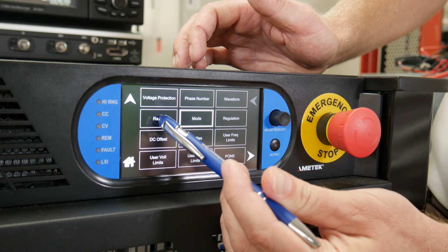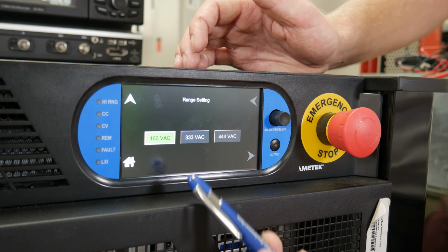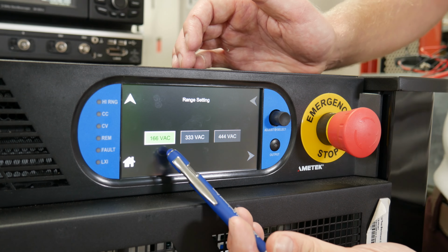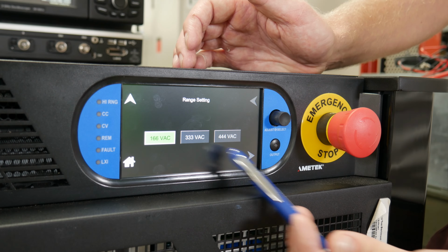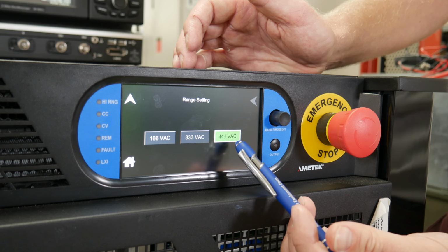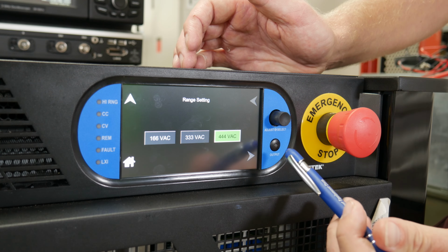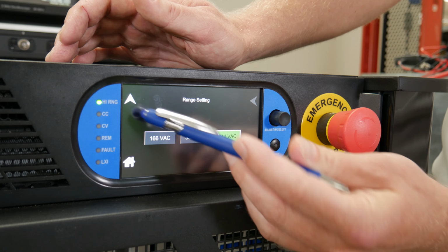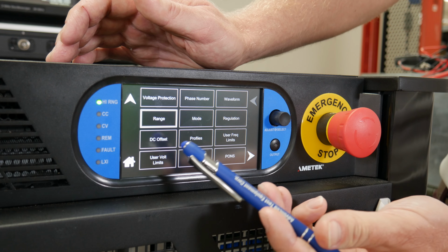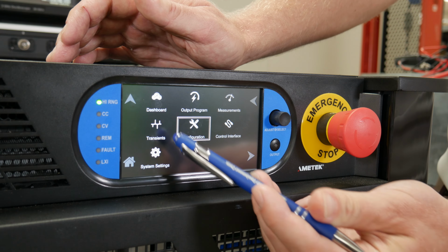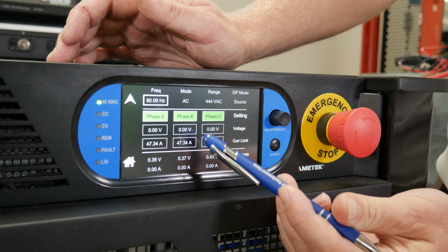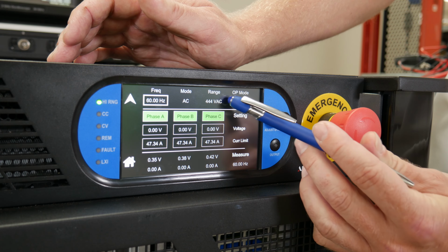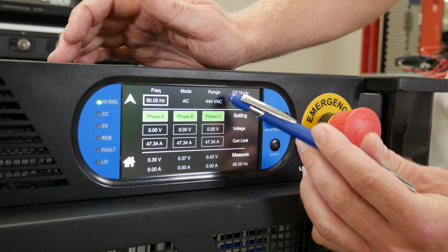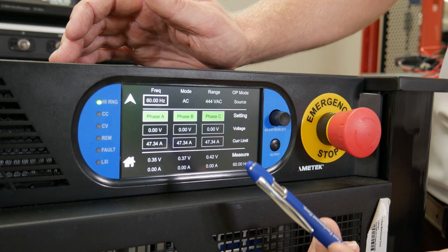You can also see that we have three different ranges within this instrument. We're currently set at the 166 setting. If I wanted to change it into that higher voltage setting, you can see that the high range indicator flicks on. Going back to the dashboard, you can also see at the top that we're in AC mode and our range is at 444 VAC.